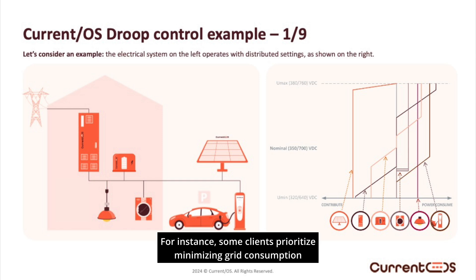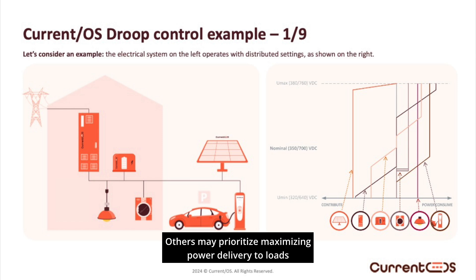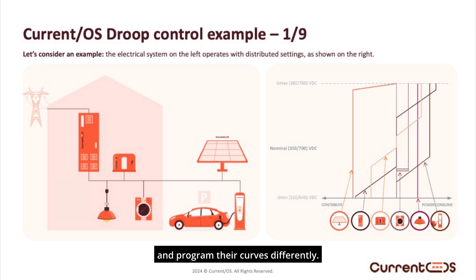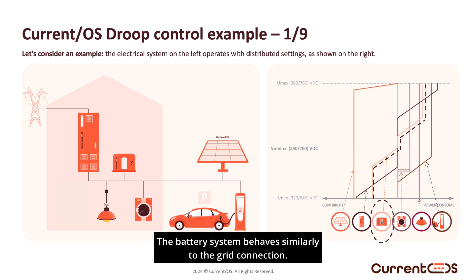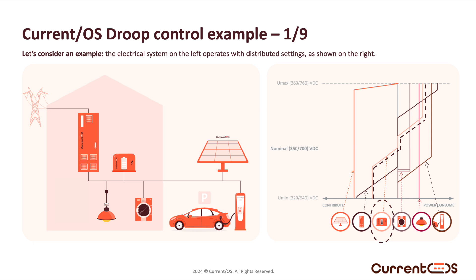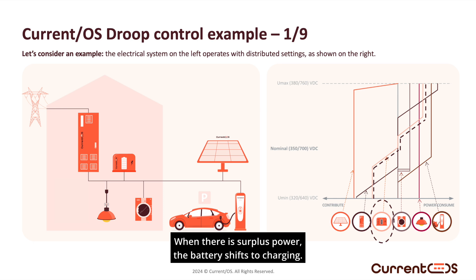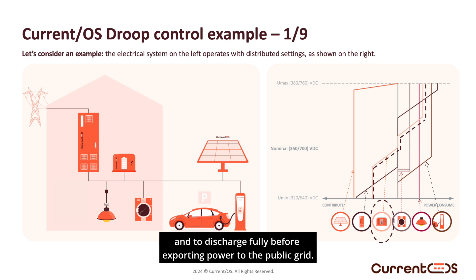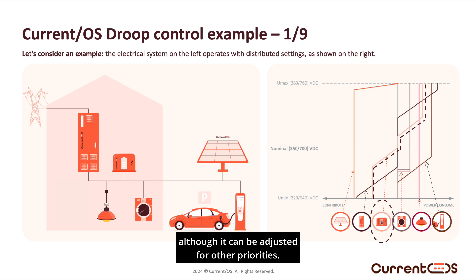For instance, some clients prioritize minimizing grid consumption and might reduce imports as soon as voltage starts rising. Others may prioritize maximizing power delivery to loads and program their curves differently. The battery system behaves similarly to the grid connection — it contributes power when voltage is low, then gradually reduces its output and eventually stops. When there is surplus power, the battery shifts to charging. In this example, the battery is programmed to contribute before importing from the grid and to discharge fully before exporting power to the public grid, supporting an energy self-consumption strategy.